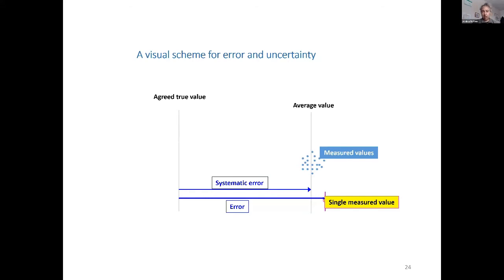So if every single one has this different error, I can make a mean and have a systematic error, which tells me I can measure so many times, but in any case, I will do this error. When I do this under calibration, try to imagine that the line, the gray line average value is the response to the instrument, and the agreed true value is the reference value given by the instrument you use to calibrate your instrument, okay, under test. But in between, you also have a random error, which is the distribution. It's random from one to the other, plus or minus, hopefully, or maybe you have everything on one side, who knows.